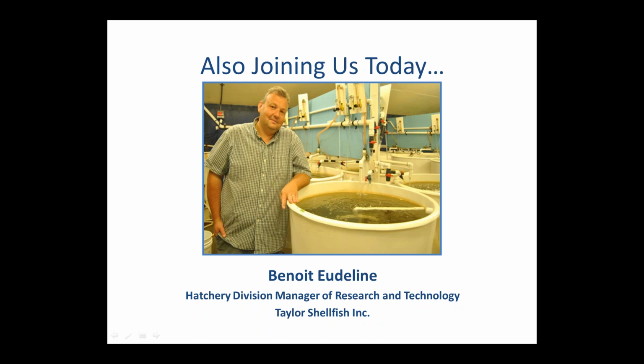But I have to acknowledge that sometimes, when we run the NBS, the TRIS buffer, and the probe is calibrated in NBS scale, when you run the TRIS buffer, the probe already reads the right expected pH, and so basically there is no offset applied. This for us is quite challenging, and I know Todd will have a lot to say about this calibration process. And that's what I have to say. In general, again, we are very happy with the Durafet probe, and these probes are quite accurate, and we like them, and we are using them a lot. Thank you.